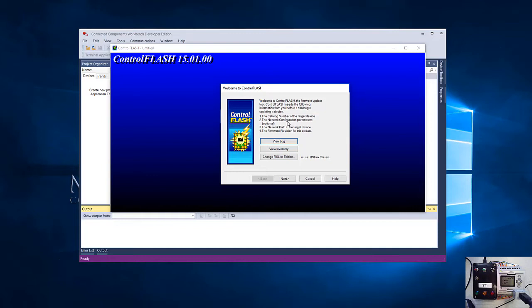The key thing about flashing the firmware is if it gets interrupted mid flash, you can brick the PLC, basically turn it into an unrecoverable failure. So this is not a thing to take lightly, but it is a tool that's necessary if something's gone wrong. More often, when you're flashing the firmware, it's because they've come out with new firmware that offers new features and you need to upgrade. In this class we won't be upgrading firmware for feature reasons, but if you lock up a major fault and can't recover from it, you may need to flash the firmware.